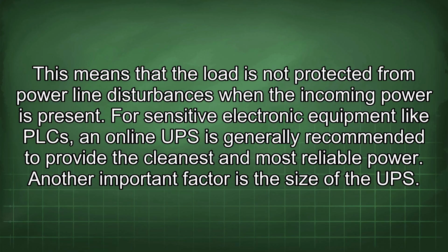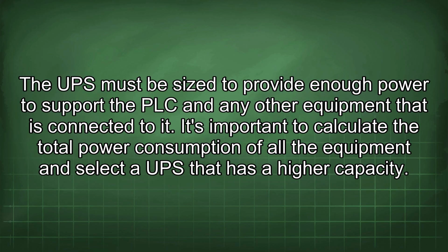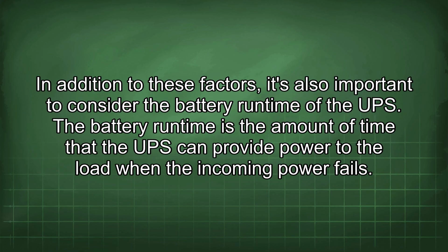For sensitive electronic equipment like a PLC, an online UPS is generally recommended to provide the cleanest and most reliable power. Another important factor is the size of the UPS. The UPS must be sized to provide enough power to support the PLC and any other equipment that is connected to it. It's important to calculate the total power consumption of all the equipment and select a UPS that has a higher capacity. In addition to these factors, it's also important to consider the battery runtime of the UPS.